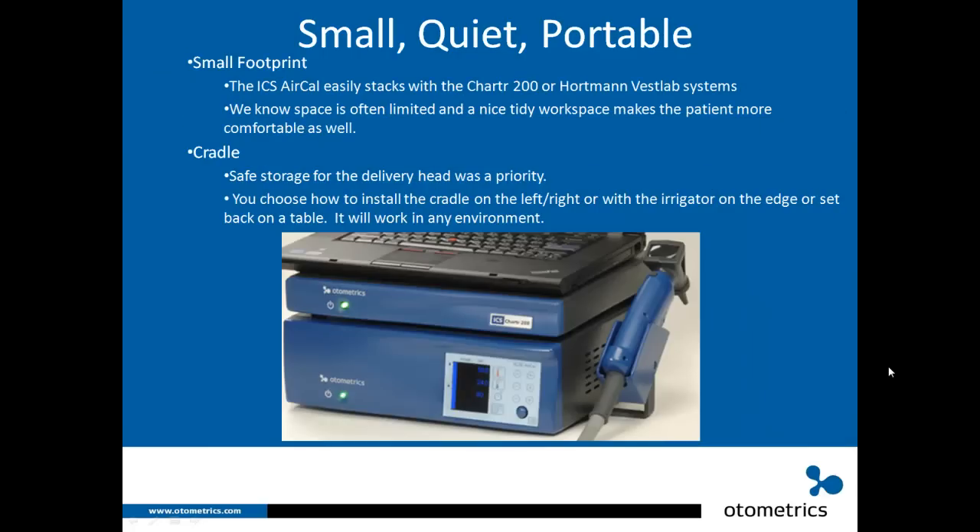Small, quiet, and portable — with a very small footprint. The ICS AirCal easily stacks onto the Chartr 200 or Hortmann Vestlab systems. Space is often limited in clinics, and a tidy workspace makes patients more comfortable. A cradle is included for safe storage of the delivery head. You can install the cradle on the left or right, and adjust it so the cable runs toward the floor at a table edge or straight out when set further back.